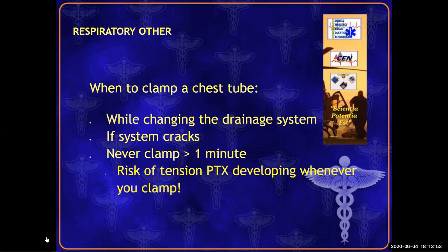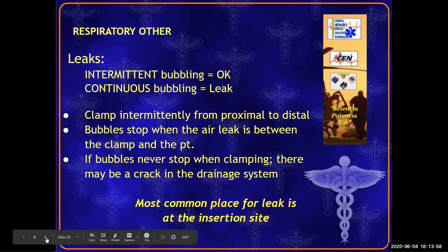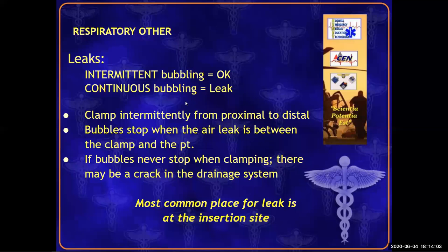because you can also build that pressure up on the inside. All right. So intermittent bubbling is okay. Continuous bubbling is a bad sign. That's when you check for a leak.